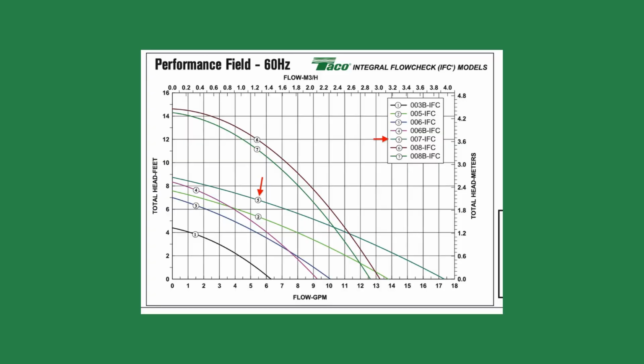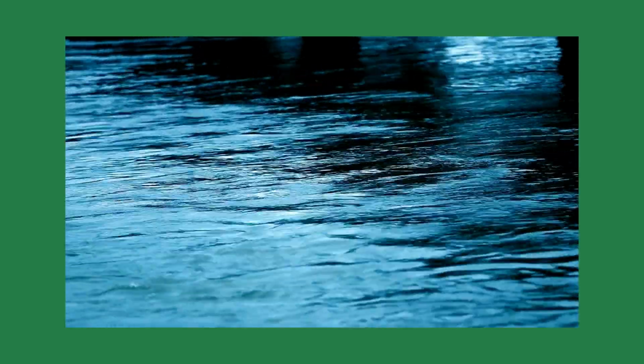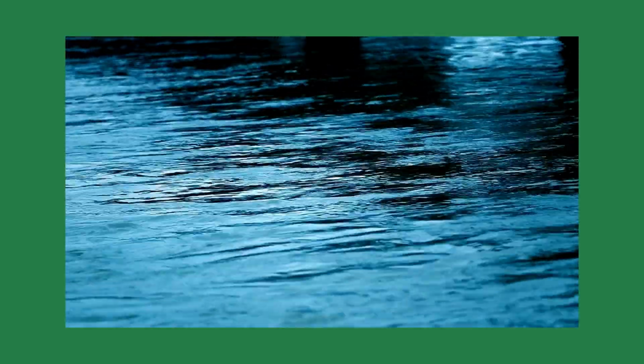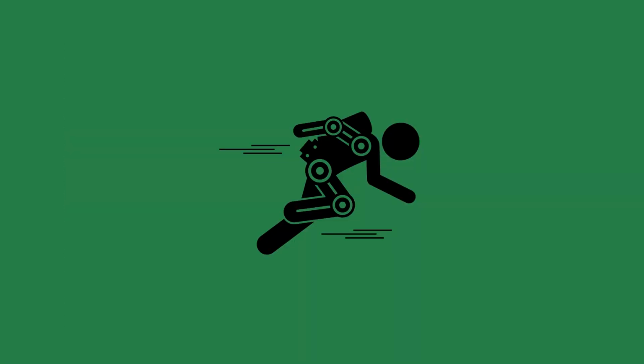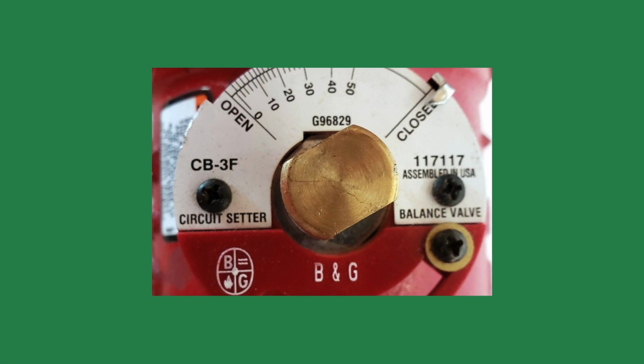In a hydronic heating distribution system, it's easy to focus on gallons per minute and feet of head, but one often overlooked yet critical factor that influences system performance, longevity, and comfort is water velocity. Simply put, velocity is how fast the water flows through the piping, measured in feet per second, FPS. Like many things in HVAC, water velocity is about balance. Too low and you get inefficiency. Too high and you risk damage.